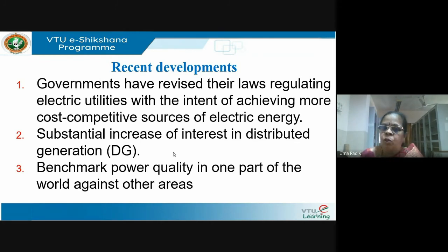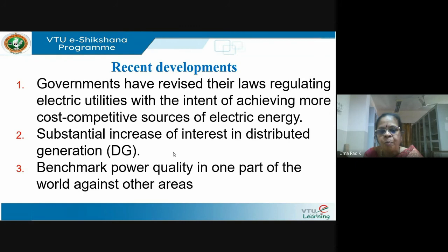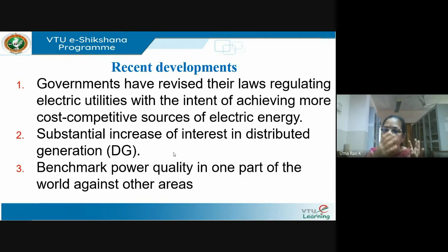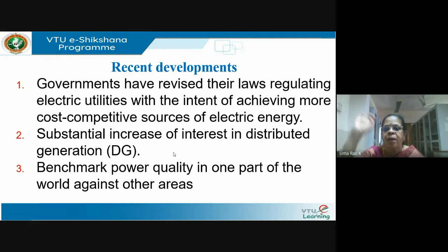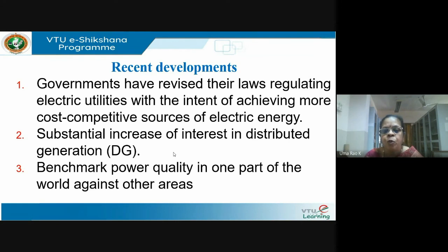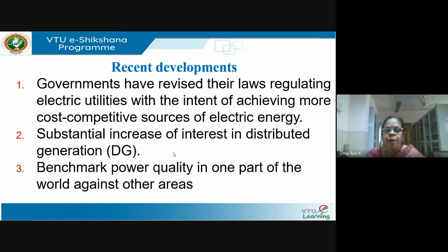A very recent development is the increased interest in distributed generation. Governments are promoting solar PV panels, solar rooftops, and solar farms — we now have very large farms of 2000 MW. The end component connecting solar or wind to the grid is a power converter, because the energy generated is not constant and keeps varying. The output of the converter must be synchronized to the grid. The problem with all these power electronics converters is they are not good in terms of harmonics — they create a lot of harmonic issues.